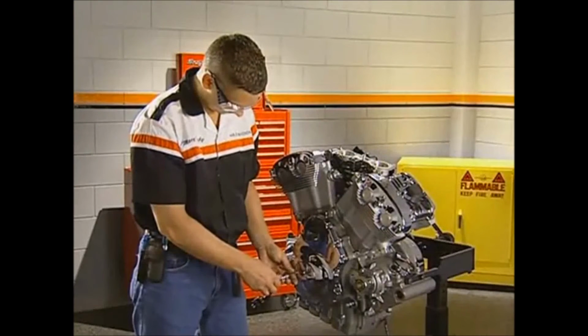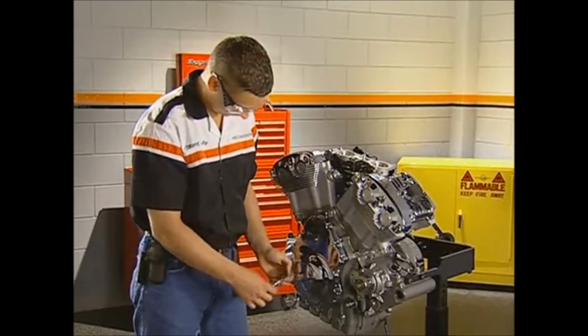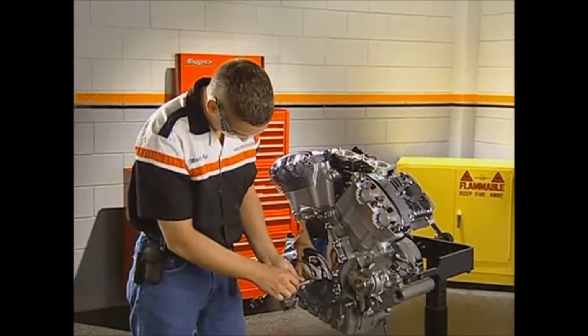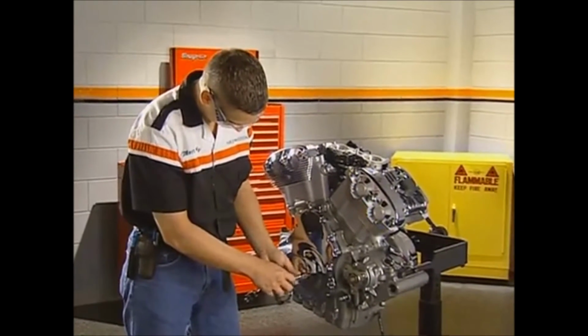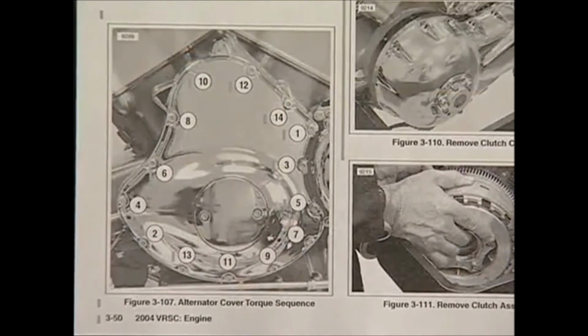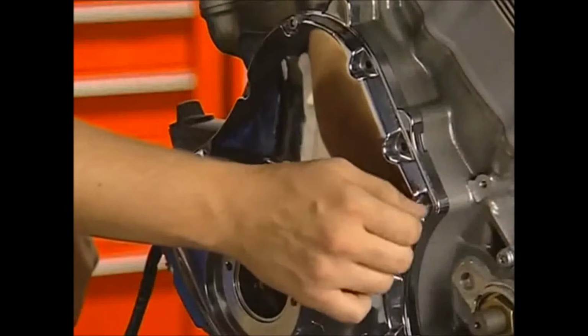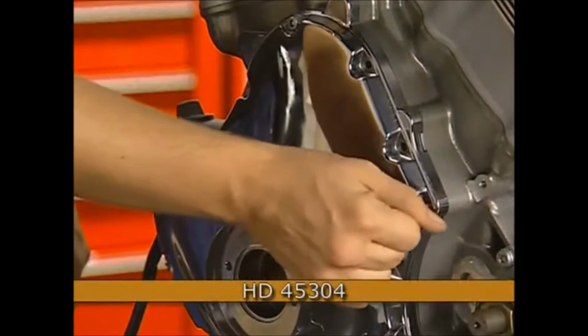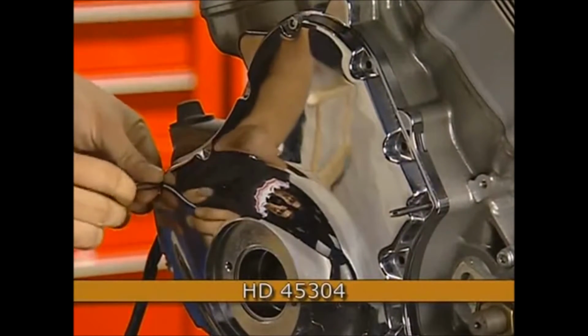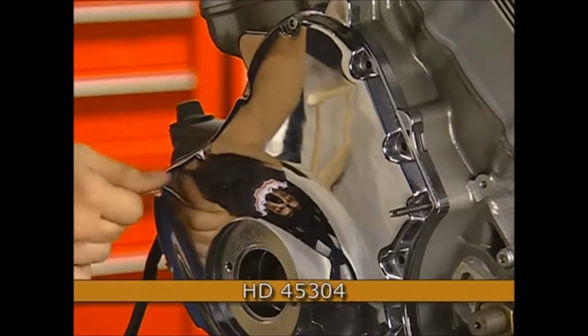The disassembly continues with the removal of the inspection cover, followed by the 14 alternator cover fasteners. Follow the torque sequence in the service manual during removal. All of the cover bolts are the same length. Two gasket alignment dowels are installed to guide the cover during removal. These pins should be on opposite sides of the cover.